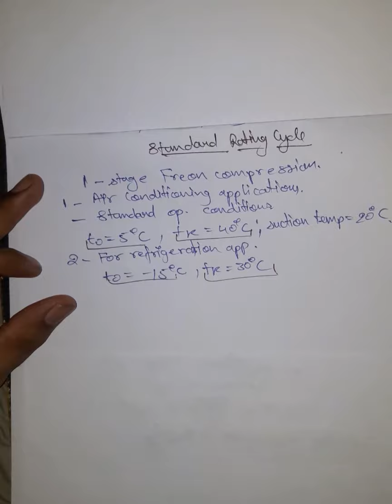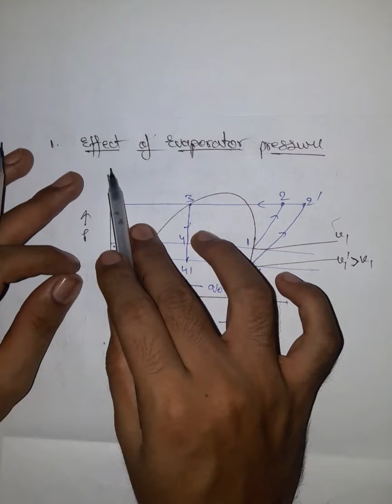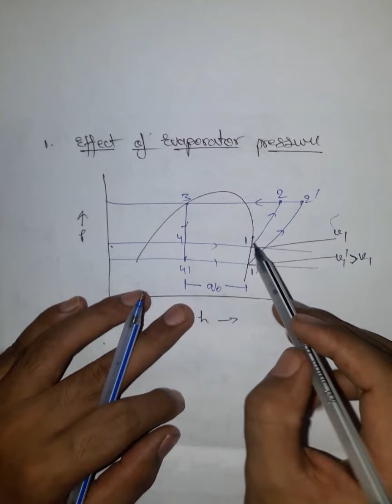So after having talked about the standard rating cycle, now we are going to talk about the effect of various parameter changes on the COP and other parameters. Here we are going to discuss the effect of change in evaporator pressure. We have cycle 1 2 3 4, the original cycle at the original operating pressures, P naught and Pk. Now we lower the evaporator pressure, that is the pressure for the process 4 to 1 is reduced, and it becomes P naught dash. Let us see what effects take place due to this change.